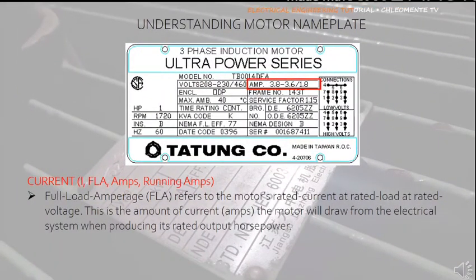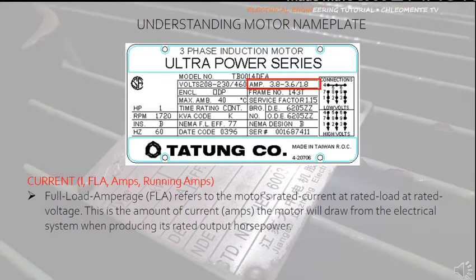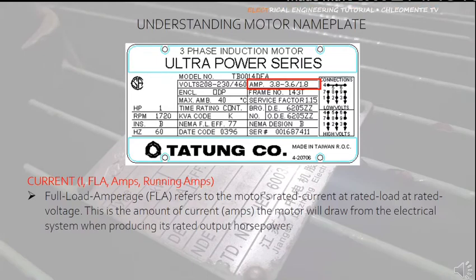Current is denoted by FLA, amps, or running amps. Full load amperage, or FLA, refers to the motor's rated current at rated load and rated voltage — the amount of current the motor will draw when producing its rated output horsepower. In this example, the nameplate shows two current ratings: 3.8 to 3.6 amperes and 1.8 amperes, corresponding to the two voltage ratings. For 208 to 230 volts, the rated current is 3.8 amperes, and when supplied by 460 volts, the full load current is 1.8 amperes.